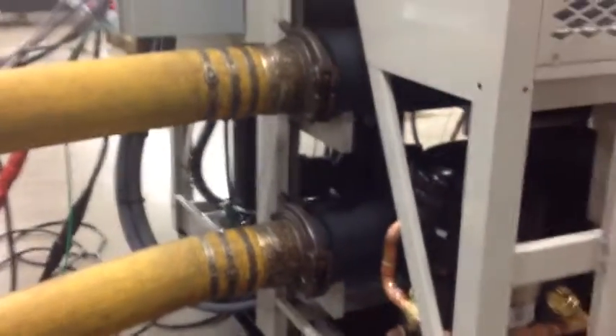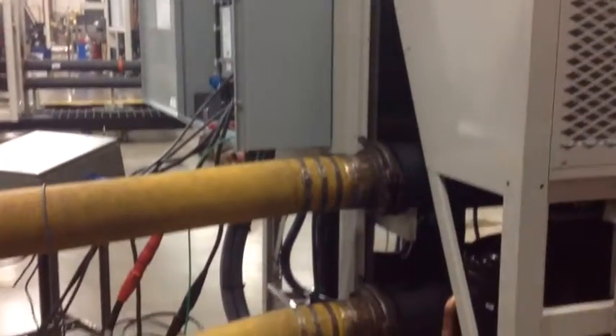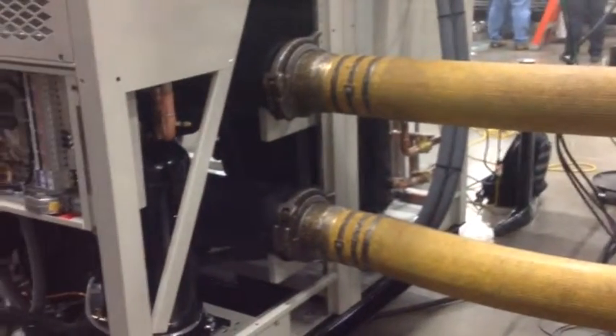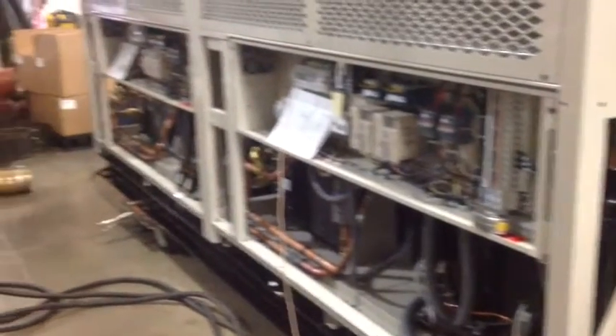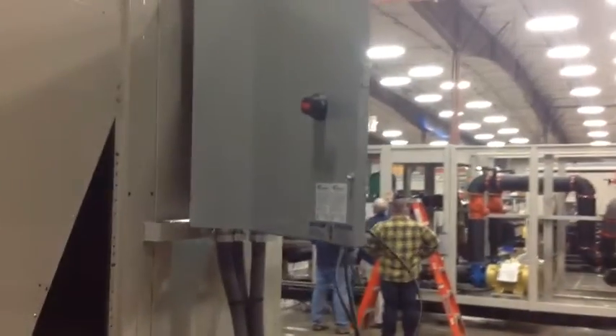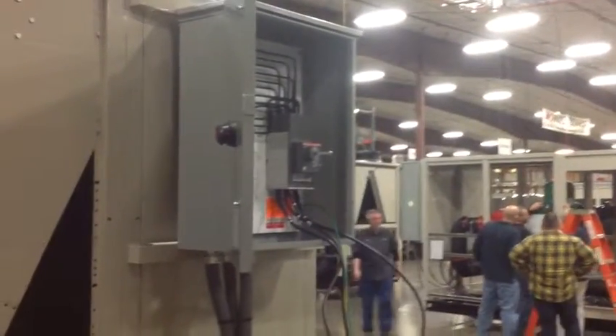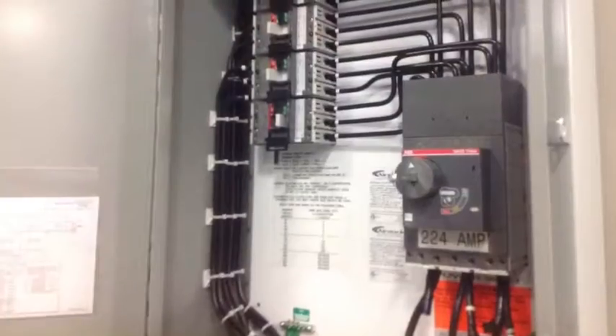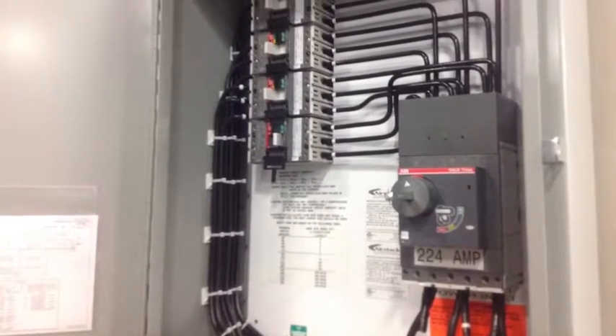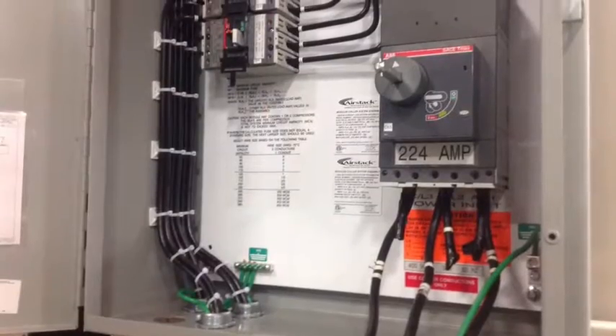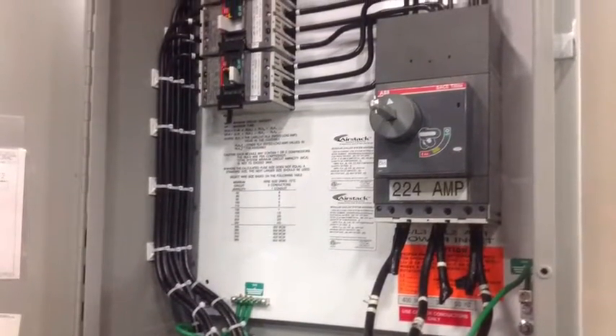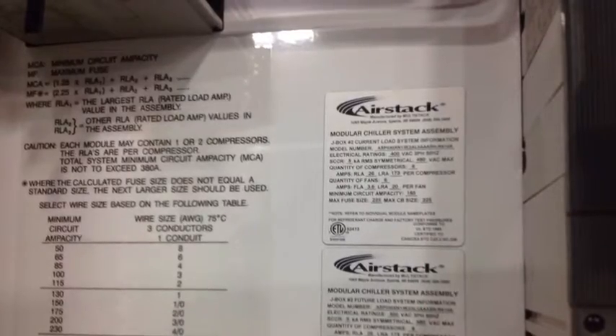Moving around to the end of the module, we'll see the single point power junction box for the pump and auxiliary array and the first 4 mechanical modules. This yellow piping that's factory piping for the test stand shows the connection to the 3 mechanical module array, which is 90 degrees around the corner of the building. Panning up, we see the second single point power connection. This is the power connection for those 3 mechanical modules. You'll note the 224 amp door interlock disconnect switch and circuit breaker, and then 4 mechanical module breakers. There is a redundant module for future expansion factored into this panel.